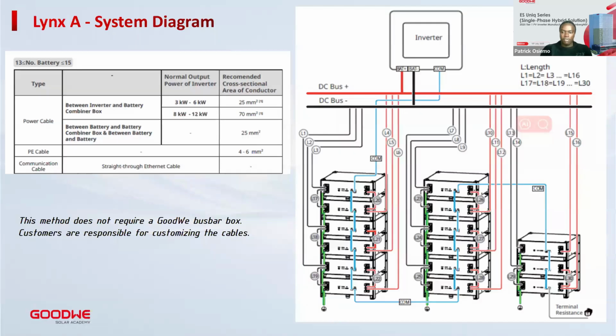So I think you'll be achieving this - yes, so here it is. The blue line is the communication cable. It goes to the first battery, then it's looped across all the batteries to the last, then in the last battery you have the terminal resistor connected. So that's how the communication will be working. The communication is only to the master inverter, but the power is to all the inverters connected in that system. Then the master inverter controls the charge and discharge seamlessly and uniformly across the inverters.